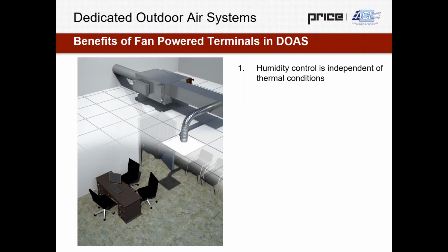Well, the first one is the fact that humidity control is independent of thermal conditions. So we have that dry bulb temperature fully being taken care of by our sensible cooling coil. And then we have our fresh air and our latent load being taken care of by that outdoor air going through the primary air valve. And those two volumes are completely independent of each other. So we can vary the volume of primary air, or we can vary the amount of airflow going through that equipment's coil fully independently of one another.